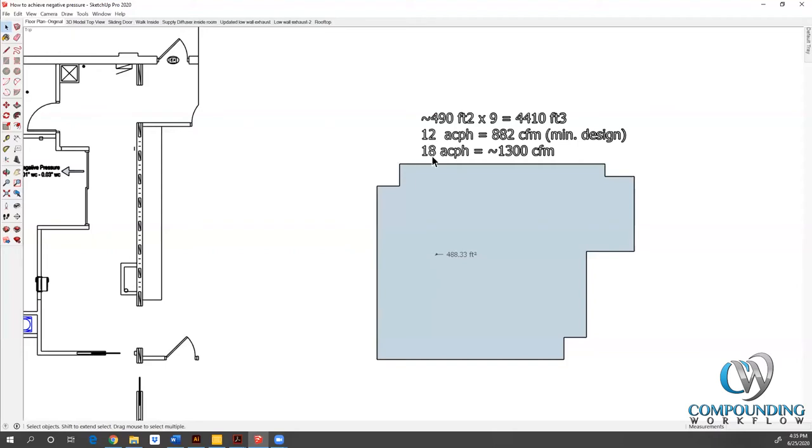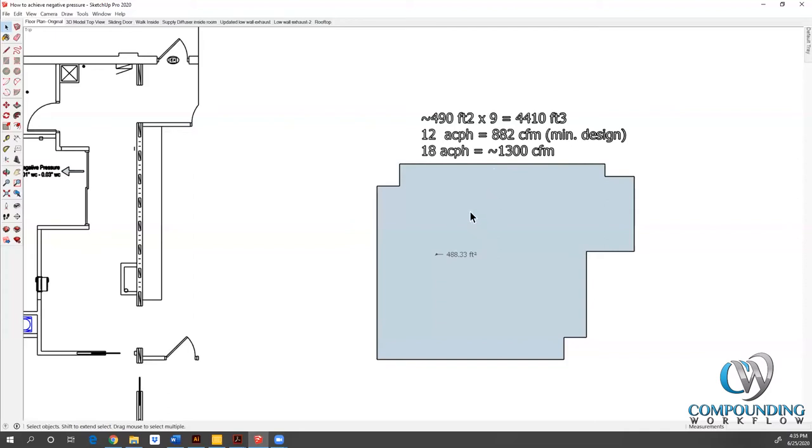People in process in July and August and all of those other factors will actually cause this room to settle somewhere in the middle, which is great because then we're above our minimum number of 12, and we don't have to worry about this room falling out of spec. We're looking at approximately 1300 CFM. The geography of this particular project was that it was actually in a very stable area, somewhere in the Midwest. They don't have a lot of fluctuations in relative humidity in the summer, which is really great.